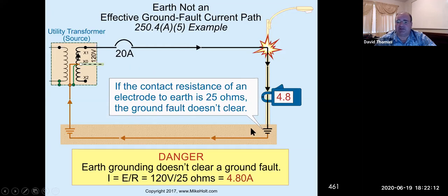But earth itself is not a good pathway. I already told you that, because resistance can be upwards of 25 ohms to ground, and you can just do the math. 4.8 amps may not be enough to trip the 20 amp breaker. In this case, we just did Ohm's law, resistance of 25 ohms. In the Sacramento Valley, I've done a lot of testing on the ground. I found that you can find 10 ohms, 8 ohms, and it also changes with the seasons. For example, in summertime, you might find 12 ohms. In the wintertime, you might find 8 ohms. Still, if you do the math, 8 ohms would put it at 15 amps, and 15 amps would still not trip a 20 amp breaker. So we cannot be dependent on earth as a way to ground our stuff, right? It does not work.